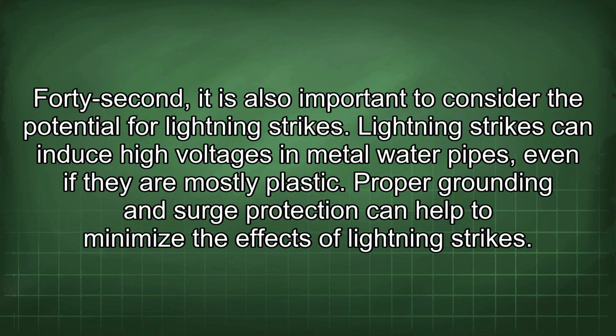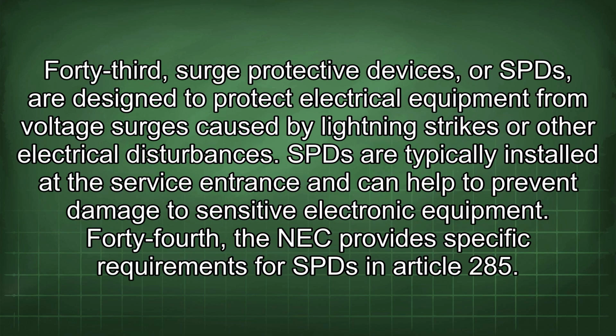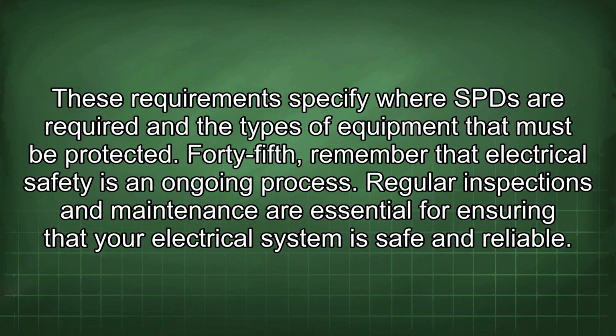42nd, it is also important to consider the potential for lightning strikes. Lightning strikes can induce high voltages in metal water pipes, even if they are mostly plastic. Proper grounding and surge protection can help to minimize the effects of lightning strikes. 43rd, surge protective devices, or SPDs, are designed to protect electrical equipment from voltage surges caused by lightning strikes or other electrical disturbances. SPDs are typically installed at the service entrance and can help to prevent damage to sensitive electronic equipment. 44th, the NEC provides specific requirements for SPDs in Article 285. These requirements specify where SPDs are required and the types of equipment that must be protected.